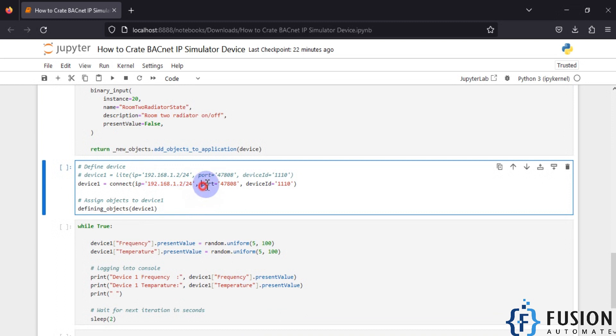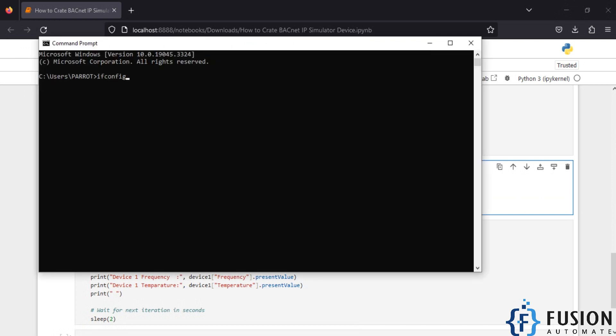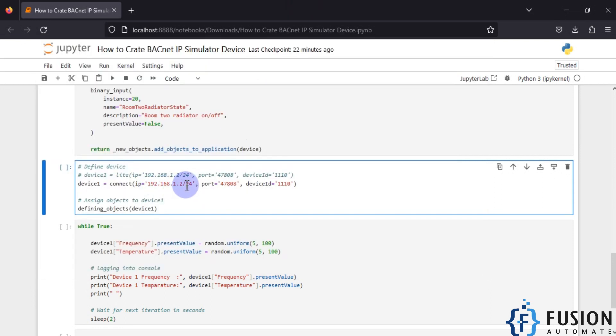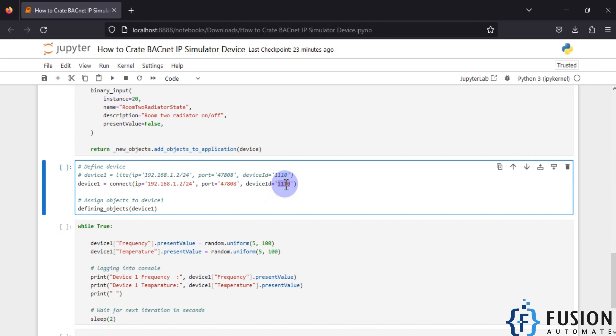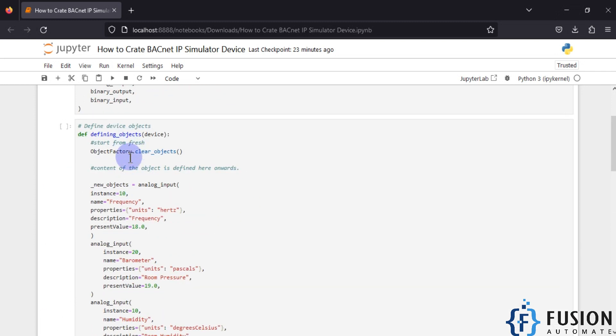Scrolling down, we have provided the IP address, subnet mask, port number, and device ID. If I open my command prompt and run ipconfig, you can see my system IP address is 192.168.1.2 and here is my subnet mask. Combining these gives 192.168.1.2/24, which is what I've provided here. This is the bac0 port, 47808, and we have given the device ID — whatever BACnet device we are creating, this will be its BACnet device ID.